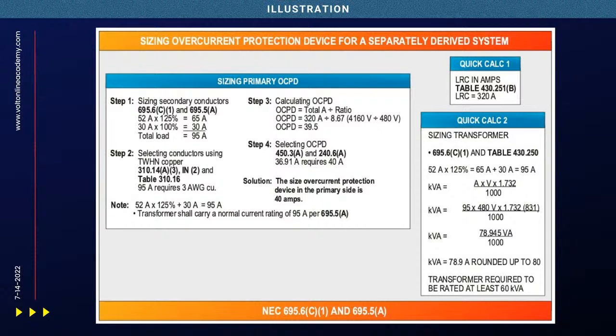Okay? Right. So now what we're going to do is we want to make sure that we're sizing this overcurrent protection device here, because I am coming off the secondary side to indefinitely hold that locked rotor current. So what you're going to do here is you're going to take.